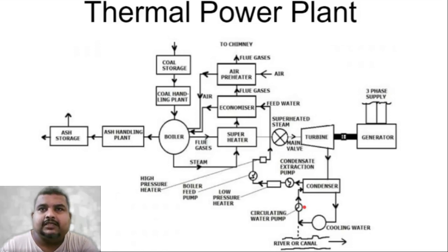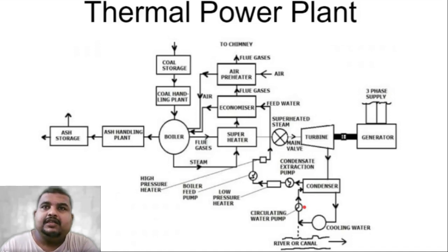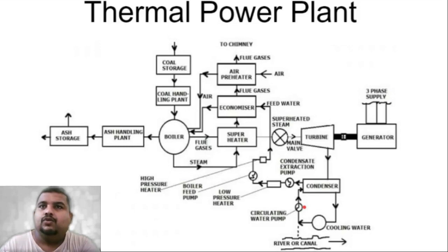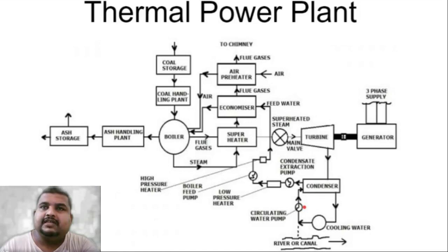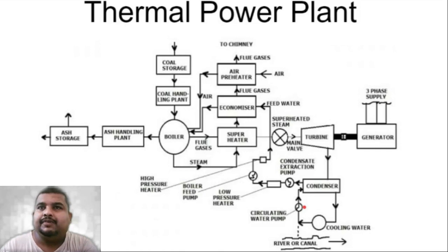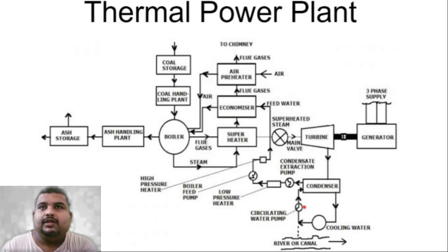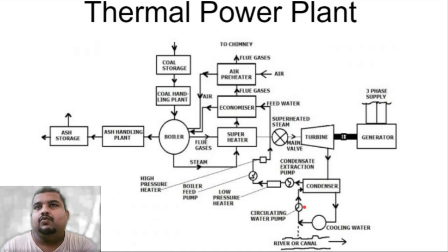After the flue gas gives heat to the superheater, that heat is again extracted at the economizer — the economizer heats the feed water using the flue gases. The flue gases then go to the air pre-heater, which heats the incoming air. After that, the flue gas goes to the chimney.